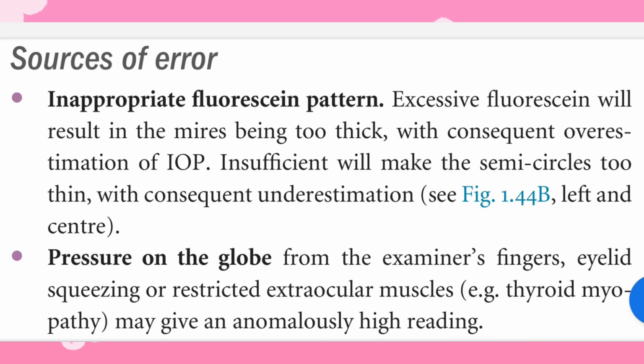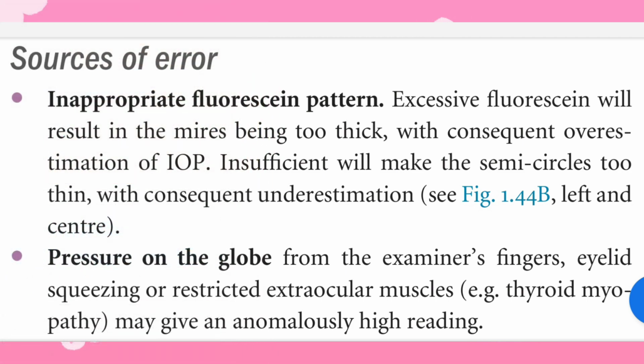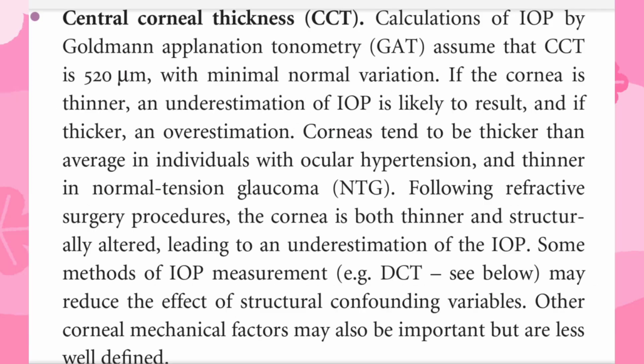Sources of error: inappropriate fluorescein pattern. Excessive fluorescein will result in the mires being too thick, with consequent overestimation of IOP. Insufficient fluorescein will make the semicircles too thin, with consequent underestimation, see Fig. 1.44b, left and center. Pressure on the globe from the examiner's fingers, eyelid squeezing or restricted extraocular muscles, for example thyroid myopathy, may give an anomalously high reading.